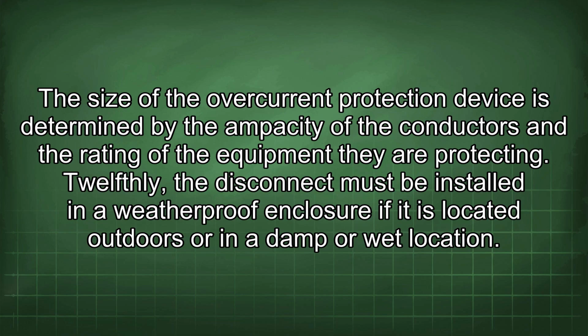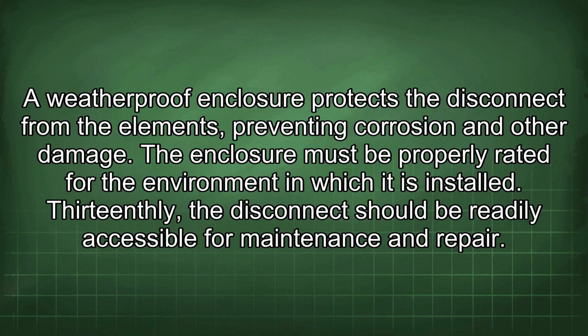equipment they are protecting. 12th, the disconnect must be installed in a weatherproof enclosure if it is located outdoors or in a damp or wet location. A weatherproof enclosure protects the disconnect from the elements, preventing corrosion and other damage. The enclosure must be properly rated for the environment in which it is installed.